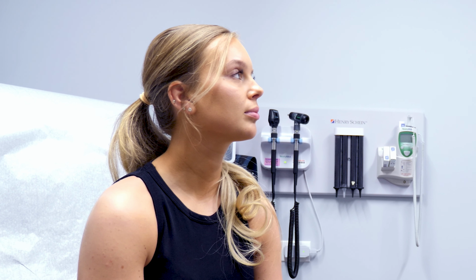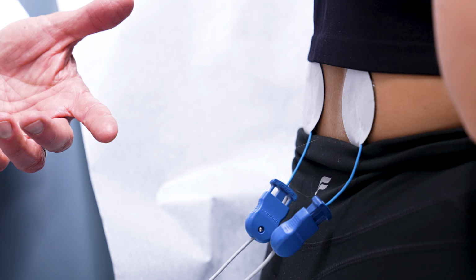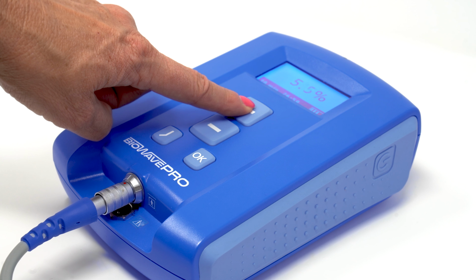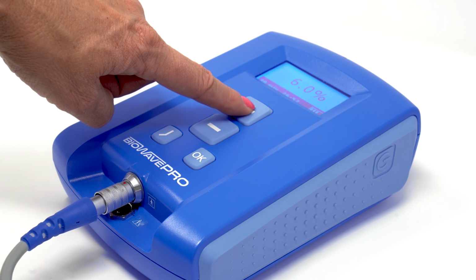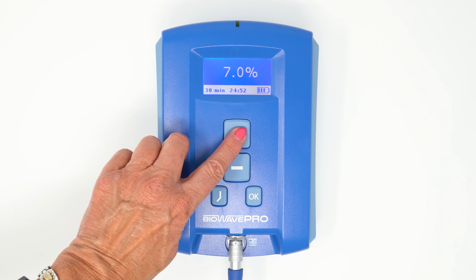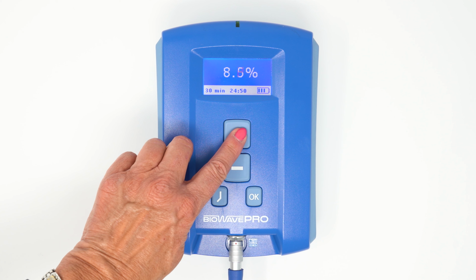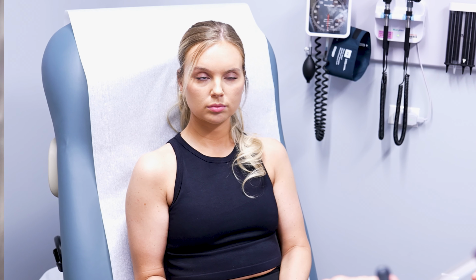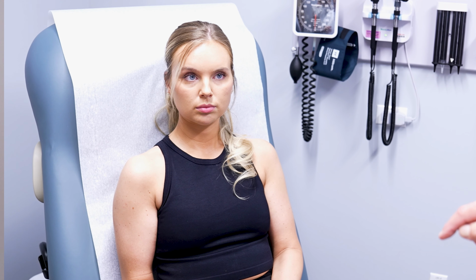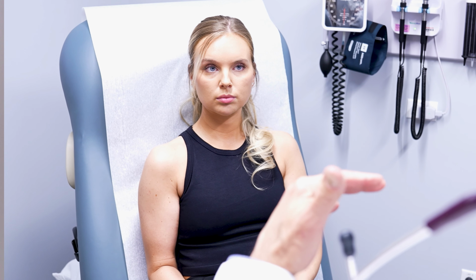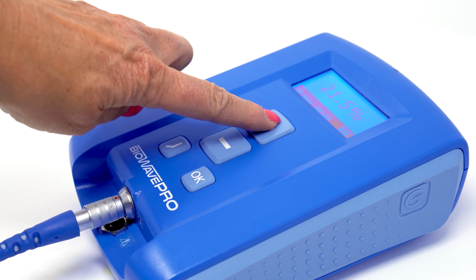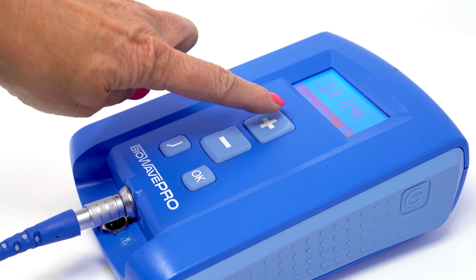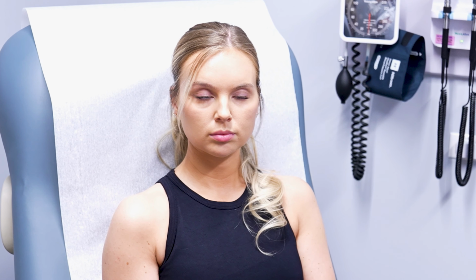The patient can be lying down or seated in a comfortable position. Depends upon what's comfortable for the patient, as well as the location of the body being treated. Instruct the patient to press the plus button to continue increasing the intensity every few minutes as the sensation fades, keeping the sensation strong but always comfortable. The patient should limit movement during the treatment and continue to feel a steady, tolerable, but comfortable tingling and deep pressure sensation throughout the treatment. The patient can continue to press the plus button with individual presses to increase the intensity at any time during the treatment if they so choose.